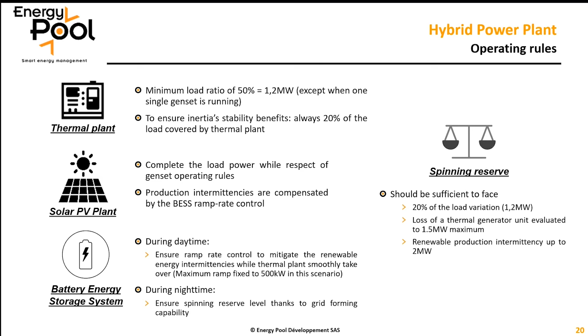Talking about spinning reserve, the spinning reserve in a hybrid power plant is the instantaneous reserve that all the distributed energy resources should be able to produce to face any event, or to face defined events. And we defined that the spinning reserve should be sufficient to face 20% of load variation, a loss of one thermal generator, and a renewable production intermittency up to 2 megawatts. Please, Jean-Pierre.